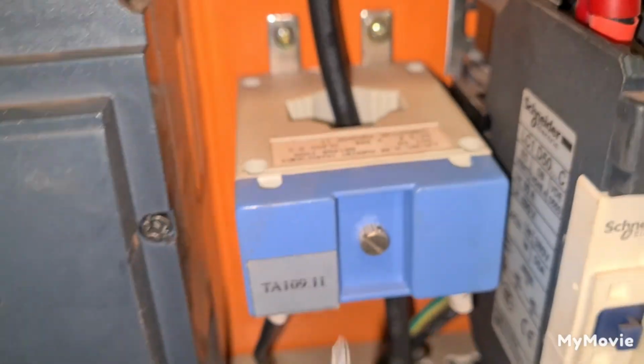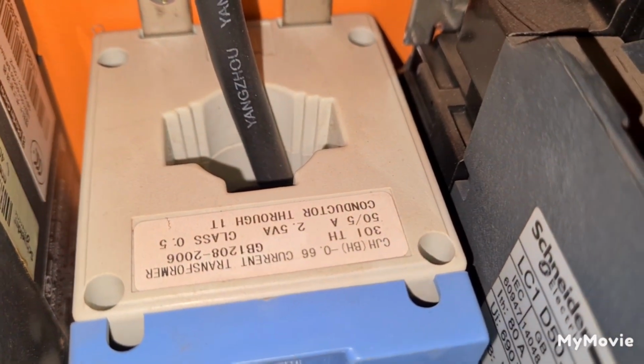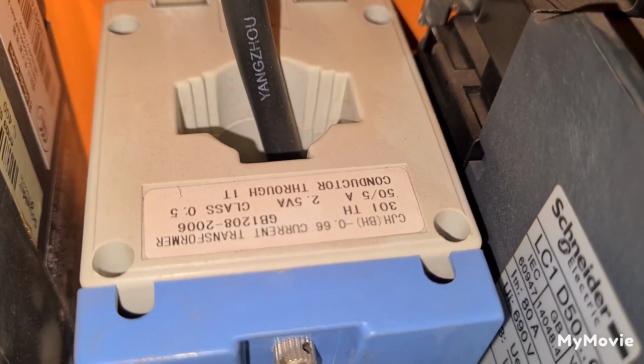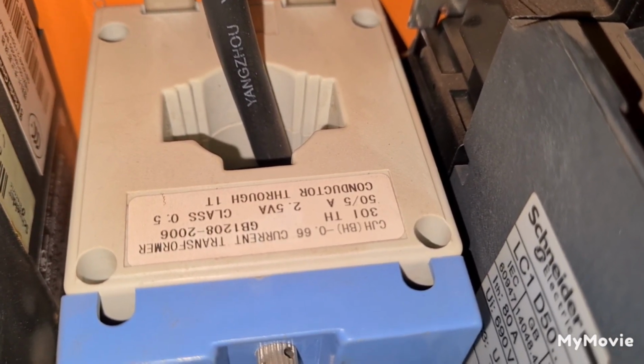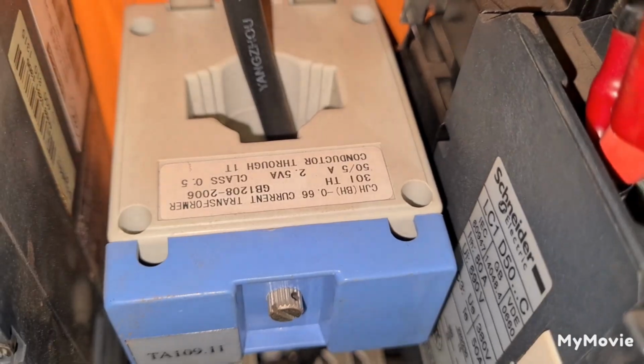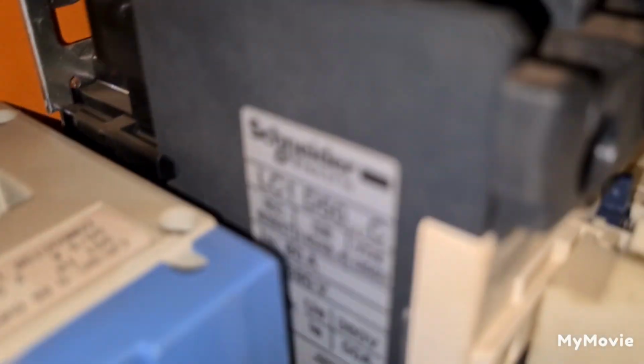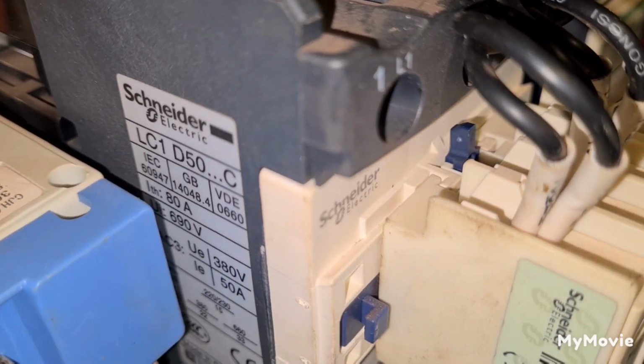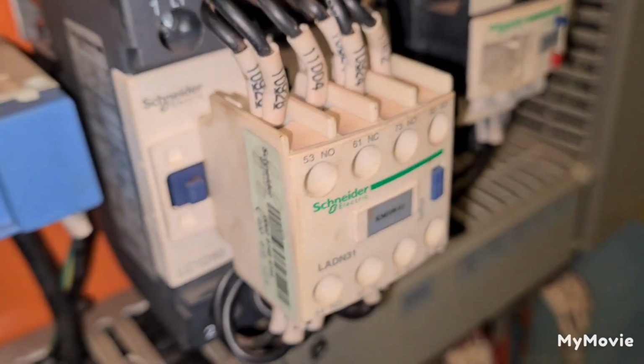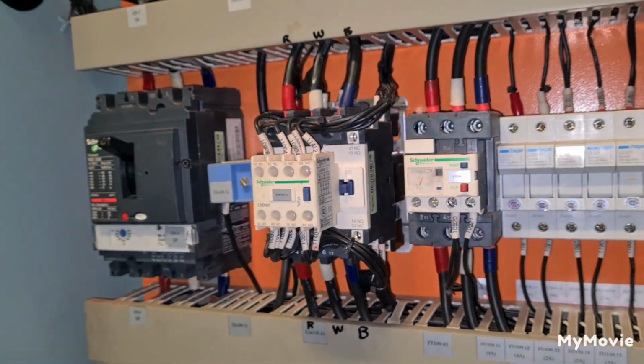The current transformer you must need to use is this one, CJH 0.66. Current transformer 50 per 5 ampere, 2.5VA. And then you must need to select the contactor with ITH value of 80 ampere. LC1D50, and you must need auxiliary contacts, overload relay. That is for our cargo hold ventilation fan.